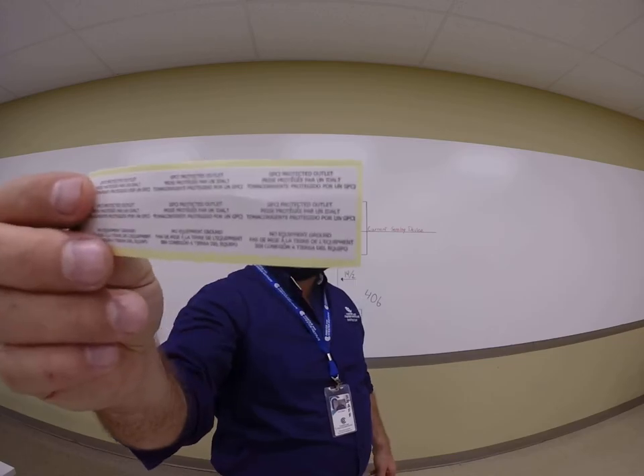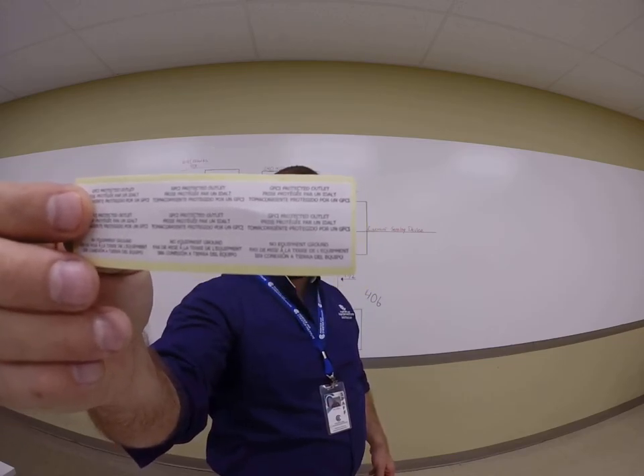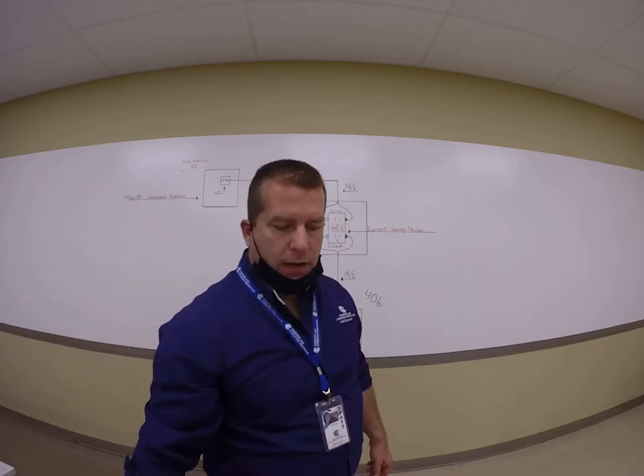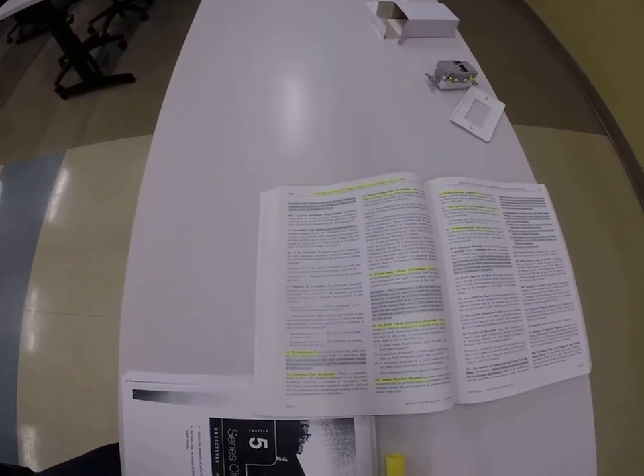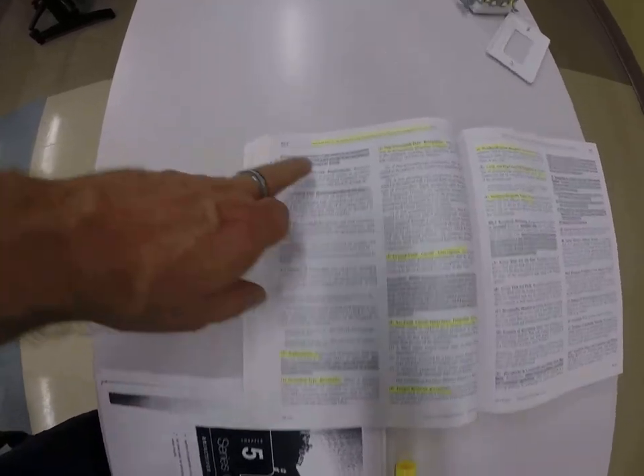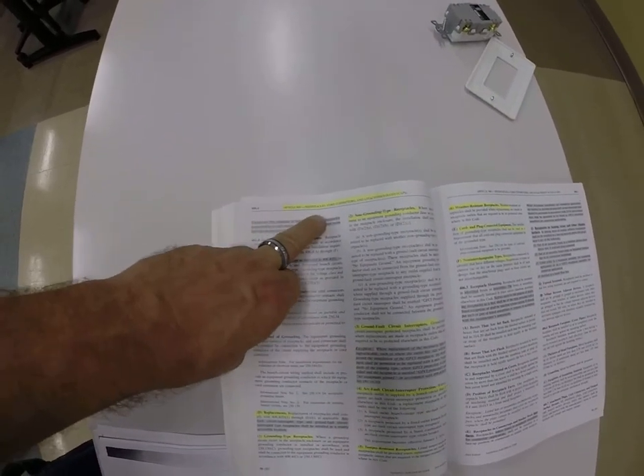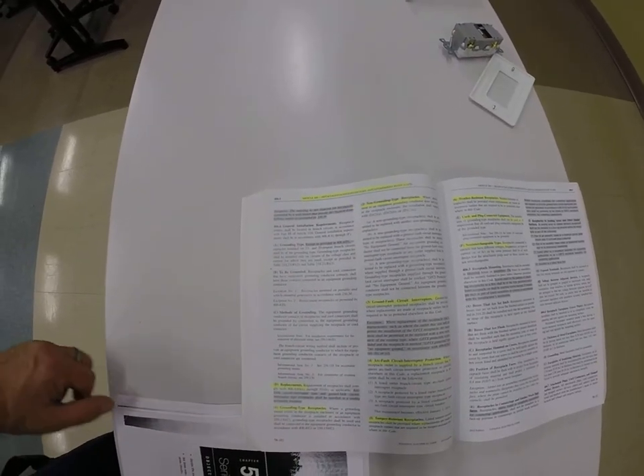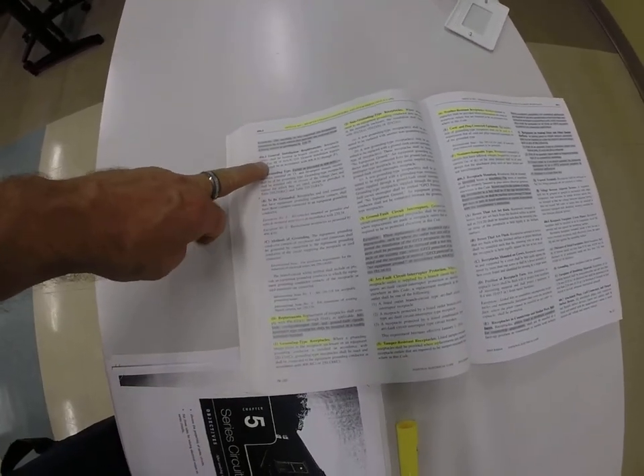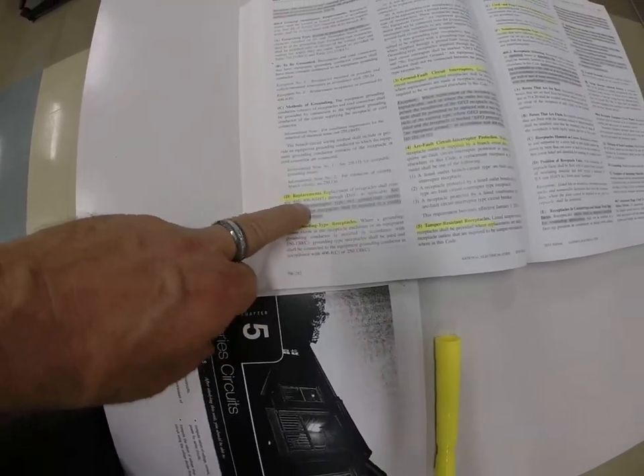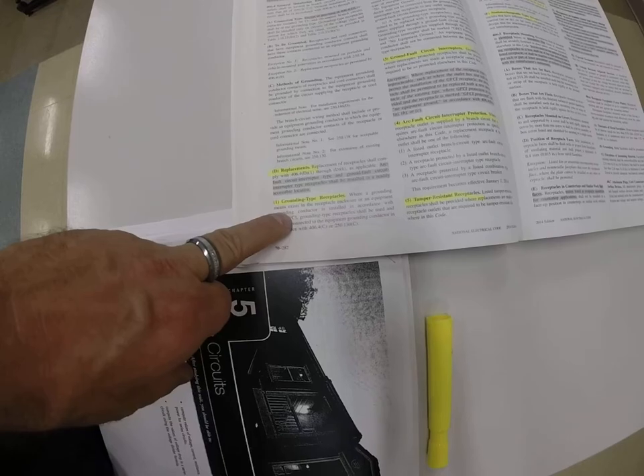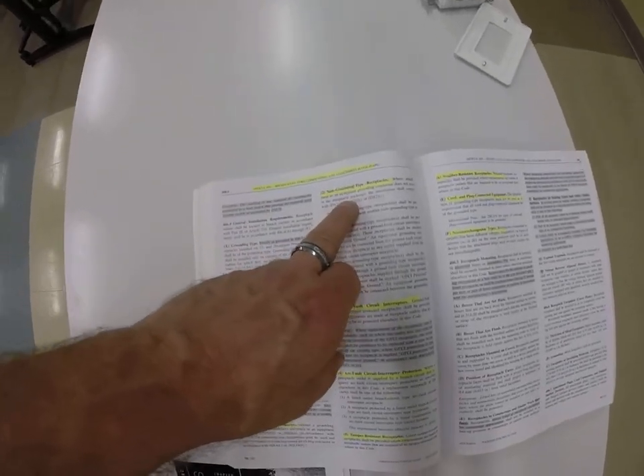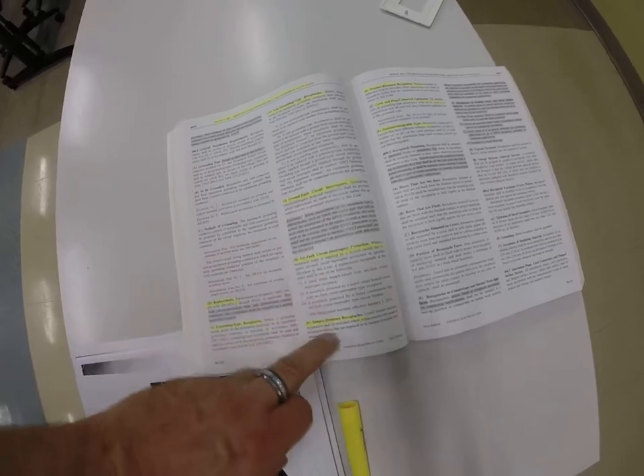And you can probably see this better than me. I don't have my glasses on. But when we're in code, I'll explain this a little bit better. And what I want to show you is where this is found in the code book. This particular code book is an old edition, but the code hasn't changed. You go to Article 406, receptacles, cord connectors, and attachment plugs. And you're going to go to 406.4(D), replacements. And there they mention if it's a grounding type receptacle, a non-grounding type receptacle replacement, GFCI, arc fault, tamper resistant, and all the others.